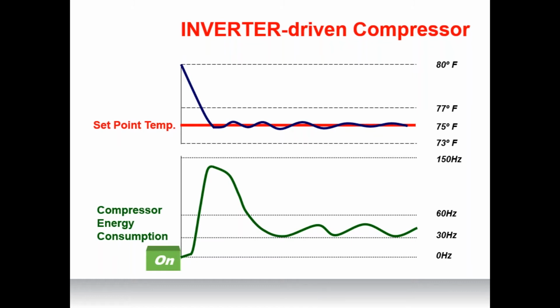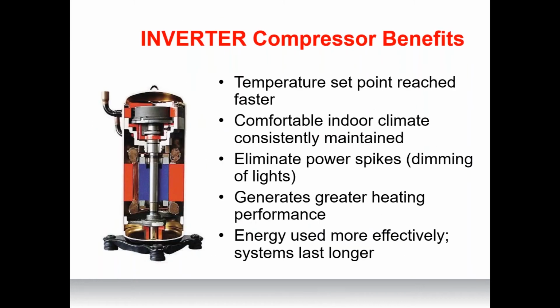Think of inverter-driven compressors as similar to cruise control in an automobile. You press the gas pedal to reach the speed limit, then you set your cruise control. Same thing here. We're going to press that gas pedal, we're going to reach our set point, and then we're going to hit the cruise control and just let that inverter compressor do its job. So what are the benefits of an inverter compressor?